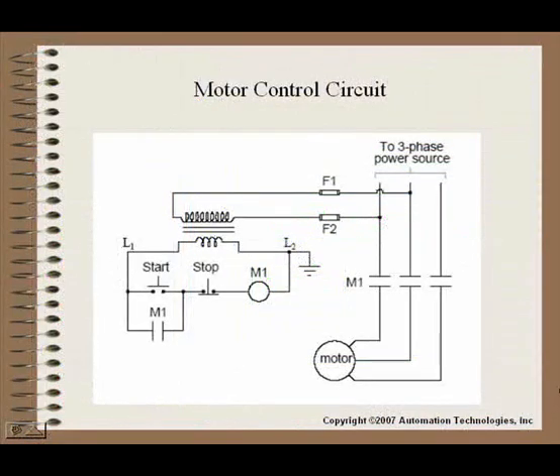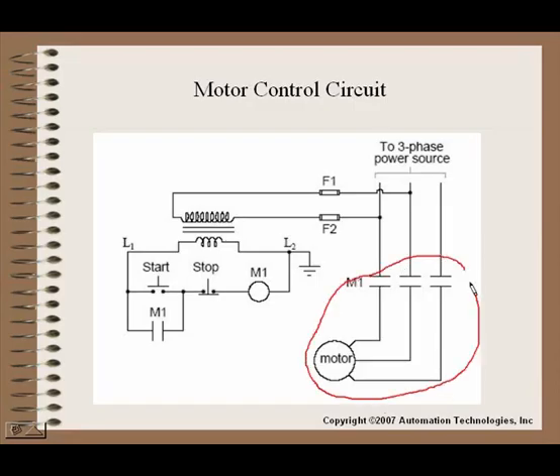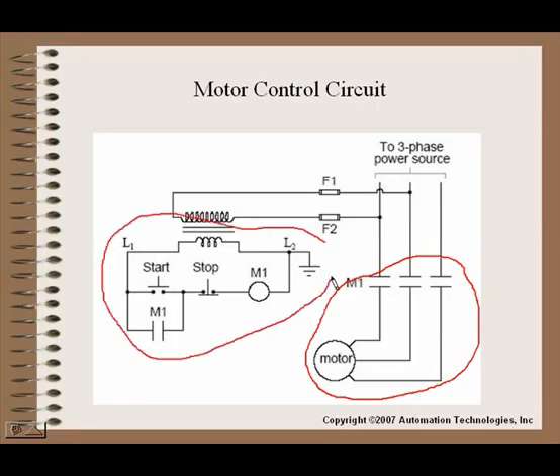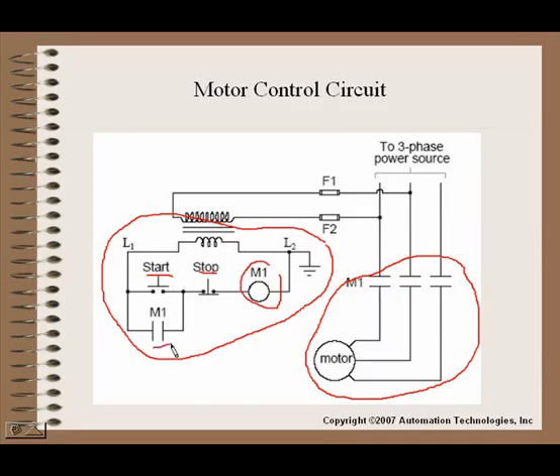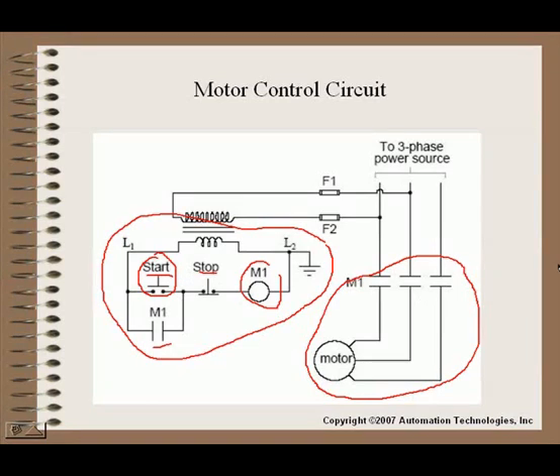Okay, let's stop for a second and maybe step a little bit back outside the PLC and talk about what's really happening. What we have here is a standard motor control circuit. You have a three phase motor right here, and you actually have your control circuit over here on this side. Now you have your start push button, the stop push button, and then you have a typical relay with a seal in contactor where when that relay pulls in, it actually seals around this momentary start push button. So that's our standard motor start stop circuit.